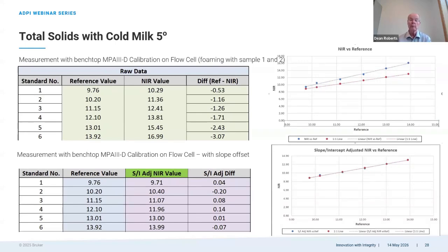Next slide. And then here's total solids with the cold milk, and here you see very clearly the slope and offset difference caused by the temperature offset. So if we look at the difference versus the predicted, it's a linear relationship, and linear relationships are nice because they can be pretty easily corrected. And on the bottom, we see the slope and offset corrected.